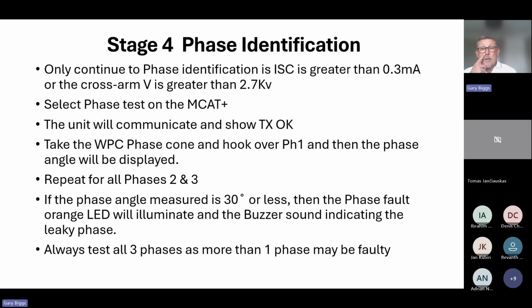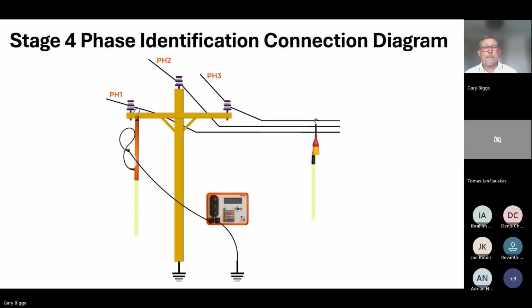And that tells you then that you need to change both of those phases. But you always test all 3 phases. Never just test one. If you test and you find one and you change it, you would still test for the other 2 just to see if there is voltage there, and that stops you having to mess about bringing the crane back down, bring the crane back up to change another phase.